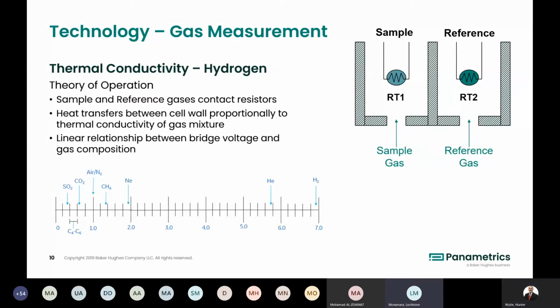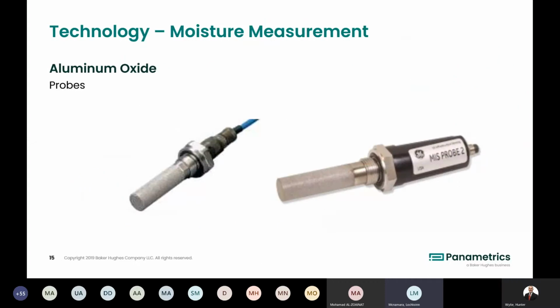No, there shouldn't really be, because fundamentally the technology is the same. I think what we didn't mention here is that over the lifetime of the aluminium oxide sensor, it will drift. So the sensor needs regular recalibration, probably every 12 months is a good interval. What the sensor tends to do is, over time there's moisture that's inherent in the sensor, and it gradually drifts off the sensor. So the sensor starts to read drier and drier over time. And often customers see that and go, well, excellent, my process is getting drier. Fantastic. But if you don't recalibrate it regularly, you end up with a false sense of security.